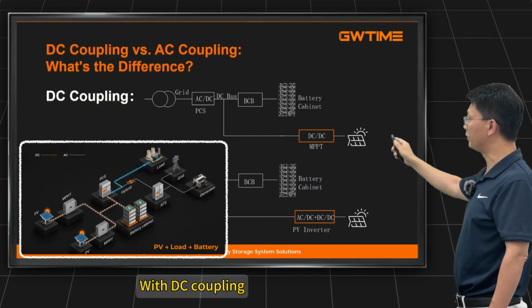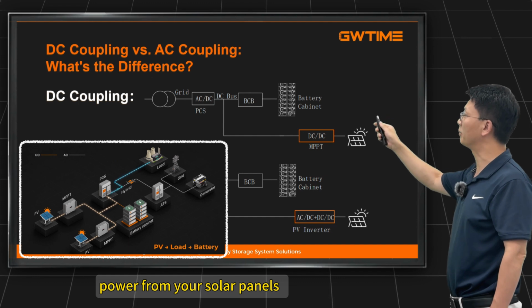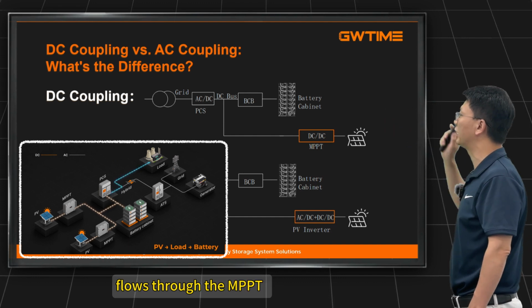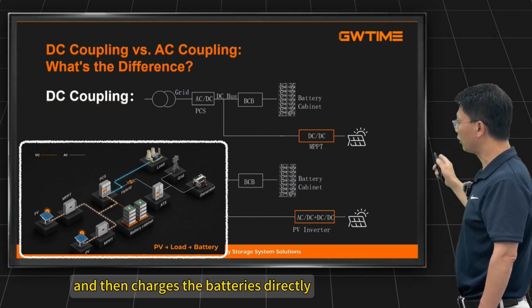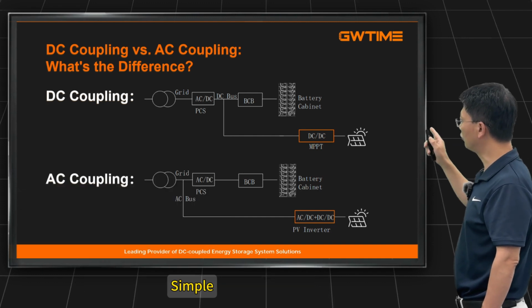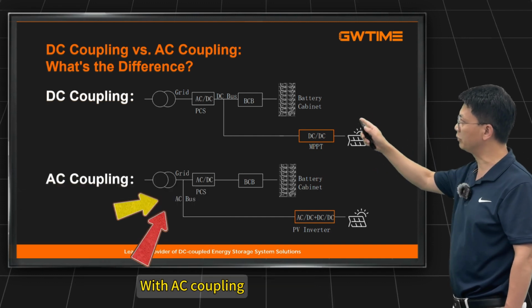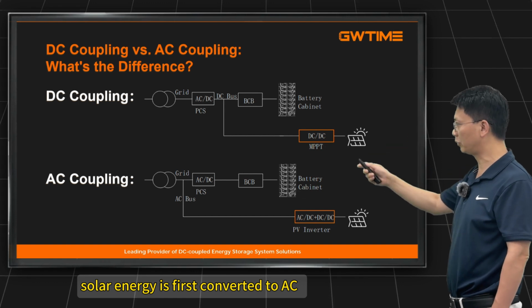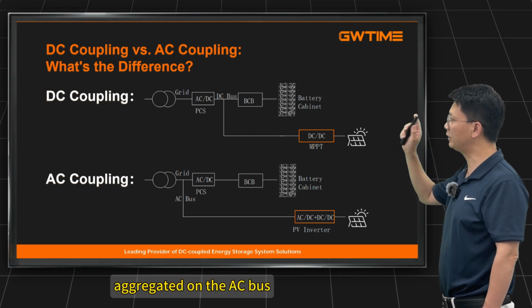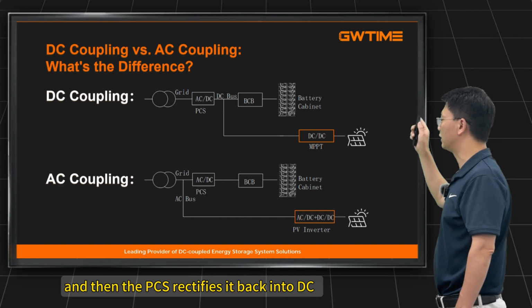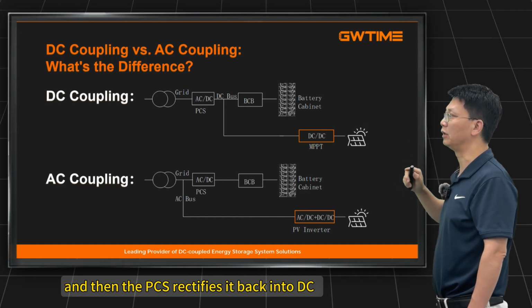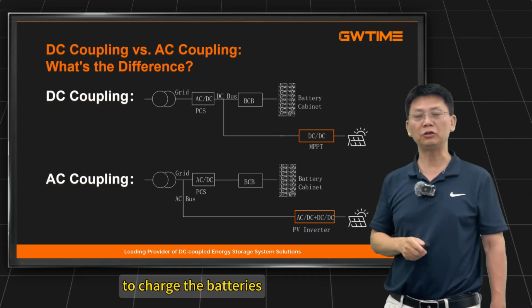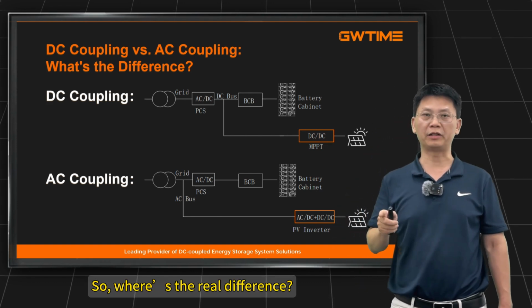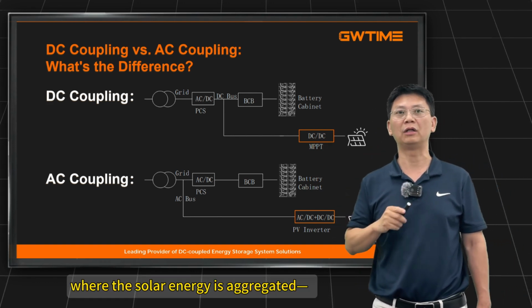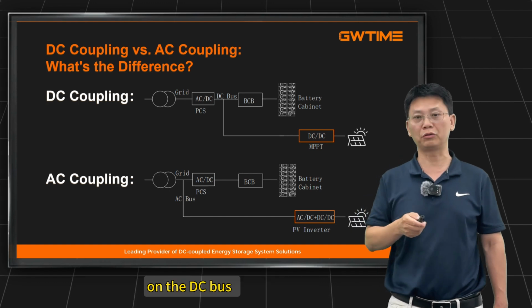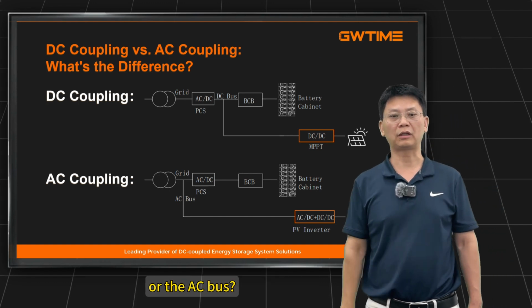With DC coupling, power from your solar panels flows through the MPPT into the DC bus and then charges the batteries directly. Simple. With AC coupling, solar energy is first converted to AC by the inverter, aggregated on the AC bus, and then the PCS rectifies it back into DC to charge the batteries. So where's the real difference? It all comes down to where the solar energy is aggregated, on the DC bus or the AC bus.